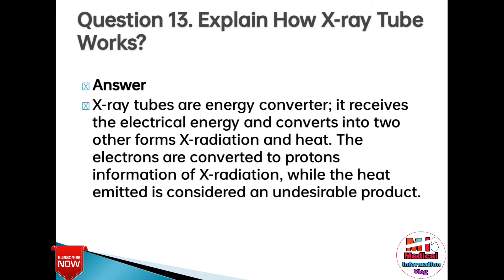Question 13: Explain how an X-ray tube works. Answer: X-ray tubes are energy converters. They receive electrical energy and convert it into two other forms: X-radiation and heat. The electrons are converted to photons in the formation of X-radiation, while the heat emitted is considered an undesirable byproduct.